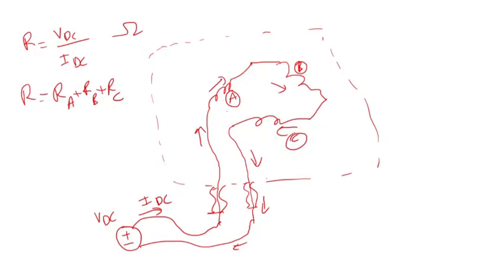But at least, if you specify the transformer to have 2 bushings with one corner of the delta brought out through these 2 bushings, then you can ask for the resistance to be measured at the factory, and you can use that value as a baseline. When you do routine maintenance in the field, for instance, you can measure this total resistance and compare it to the test report. So these are at least 2 tests you can perform on this stabilizing winding. There's winding insulation resistance and this winding resistance. You can also do a power factor test.